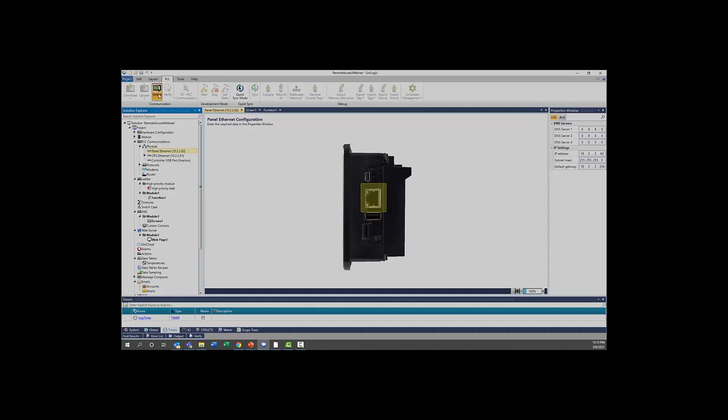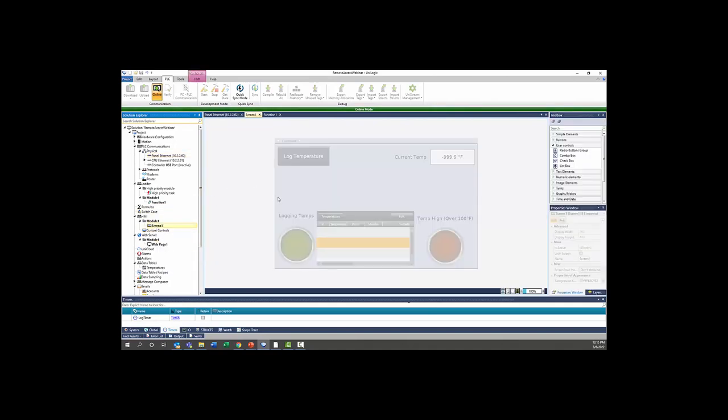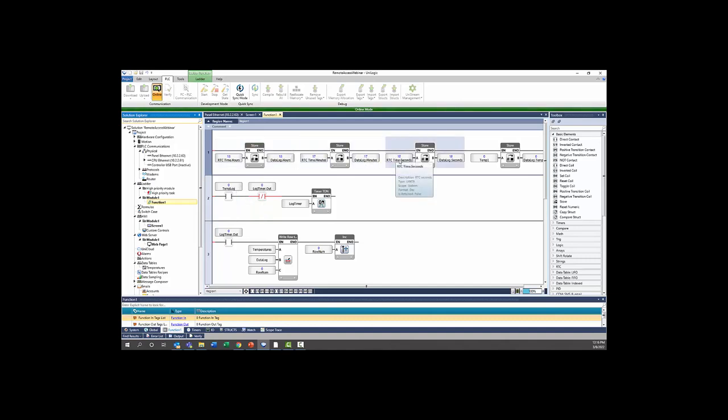Once you have communication, you'll see that my screen here has gone grayed out. Now what we can do is we can go to the screen, and you'll see that it is also grayed out. This would indicate that we are currently in online mode. You can't make any edits to the HMI while you are in online mode, nor can you make any changes to the ladder. You'll see that certain rungs here are red, and there are now blue numbers located over many of the tags. This is showing you the current values of those tags within the PLC. Like up here, you can see as each second passes, the real-time clock time in seconds changes live with the values currently in the PLC.